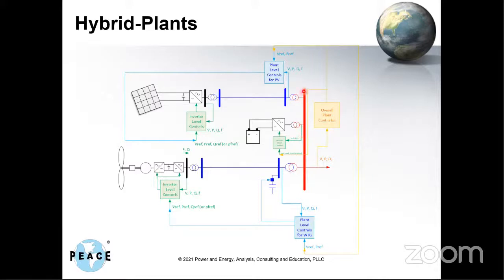You can do whatever you wish: control P, Q, V, primary frequency response, fast frequency response. Obviously each one of these elements will have its own inverter level controls, right? And then the wind portion of the plant will more than likely have its own plant level controls. And the solar portion of the plant will have its own plant level controls for the solar. And then you will have an overall plant controller that controls everything. And then you can regulate voltage at this POI. You can have primary frequency response. You can have fast frequency response. You can do all of those.